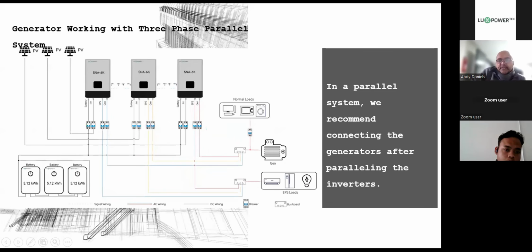And we have a look at the infographic for your 3-phase parallel, exactly the same as the single phase, but obviously the difference here is the power routing. Here we have a 3-phase generator going through your 3-phase breaker, and then each inverter will get a phase. Okay, so there's the red phase, there's the yellow phase, there's the blue phase. And once again, the generator is adequately sized to take load and charge the batteries. But bearing in mind, our new feature now will also allow for generator boost with PV.